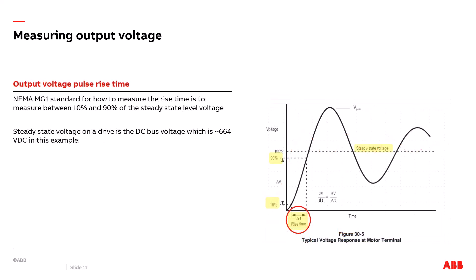Besides peak voltage, we can also measure rise time — how long it takes for the transistor to turn on. Before showing this on an oscilloscope, let's cover the standard for measuring rise time, as it's not obvious. The image on the right is from the MG1 Part 31 standard for motors, which details exactly how to measure IGBT rise time for a VFD running a motor. Rise time is measured as the time between 10% and 90% of the steady-state voltage, which is the DC bus voltage of the VFD.